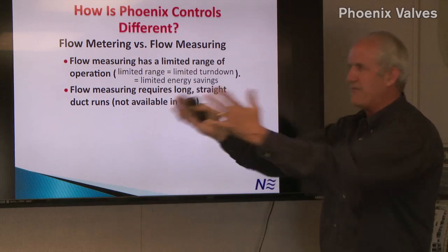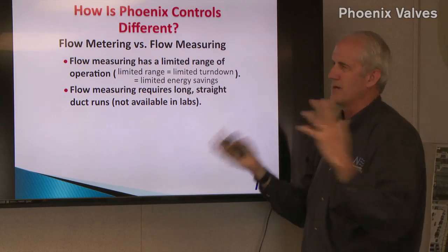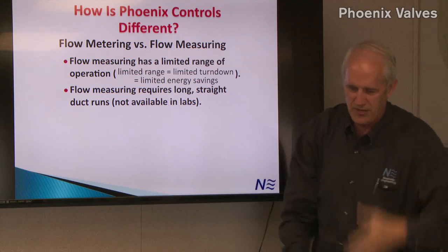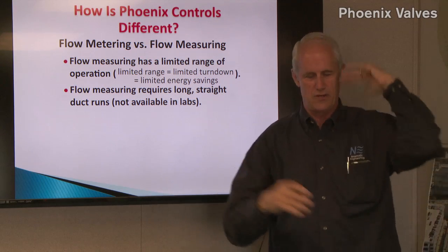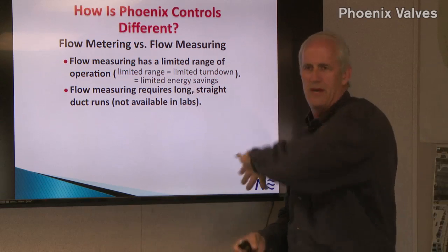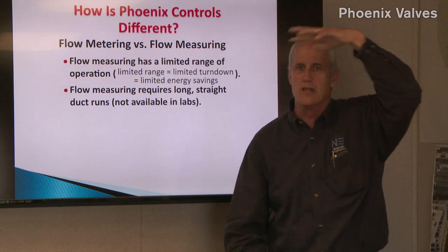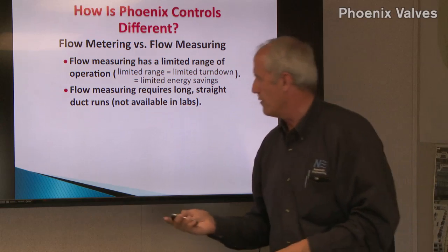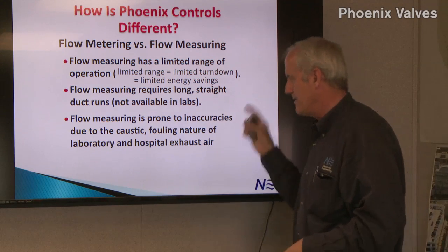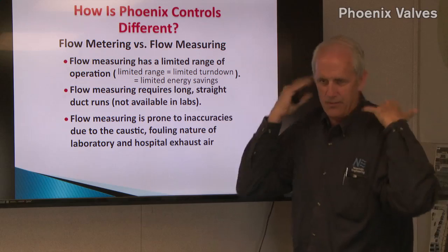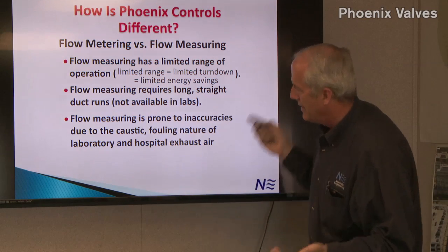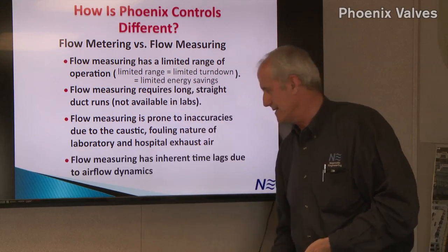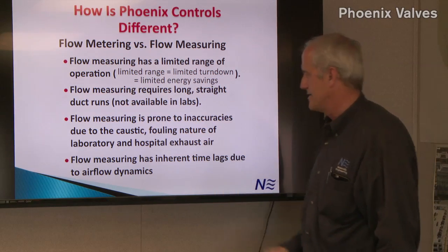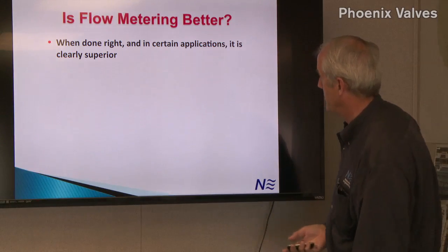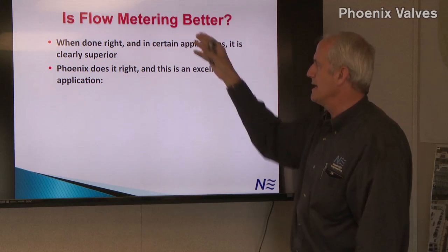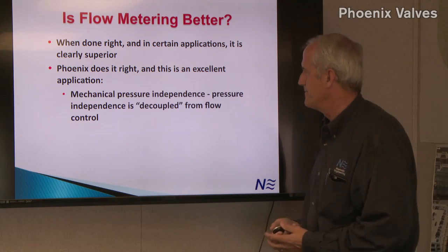And for flow measuring, you have to have what's called fully developed flow. You have to have long duct runs. Well, you don't often get that. In fact, you'll find in your vivarium, you have a lot of vertical up and down valves where you're just dropping down into the vivarium and pulling up out of the vivarium, and you don't have a whole lot of real estate to work with in terms of developing your airflow. And flow measuring can be messed up by dander, for example, on the exhaust side. The Phoenix valve doesn't have a problem with any of these things. And there are time lags, which don't apply. So flow metering is better when it's done right, and Phoenix does it right.